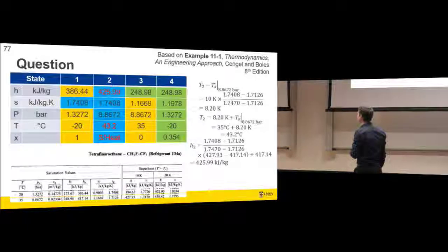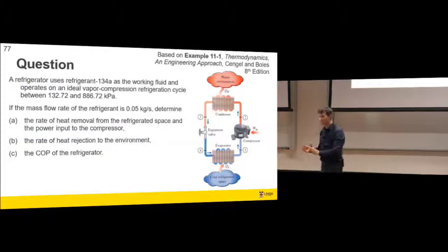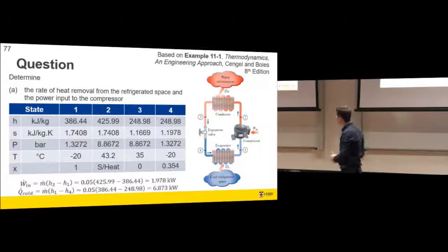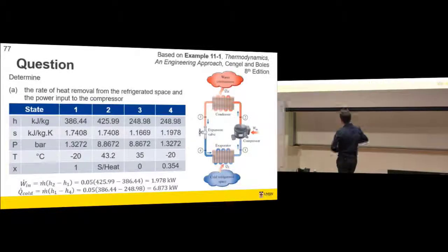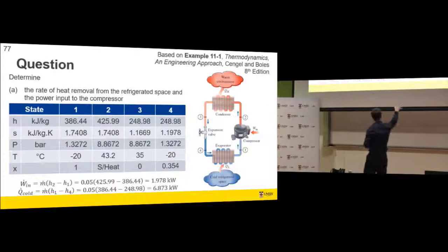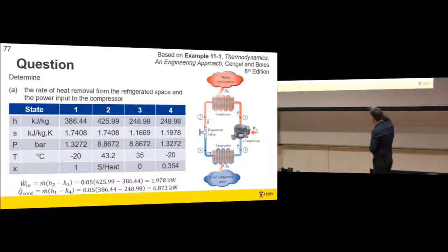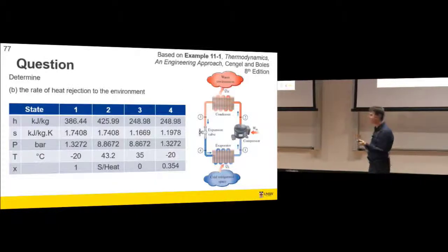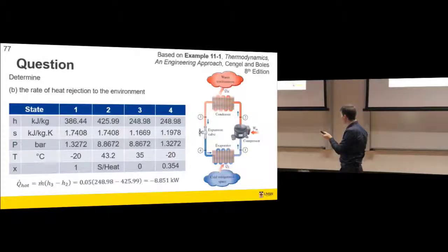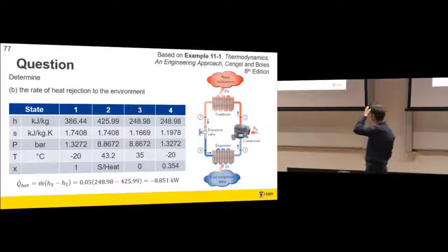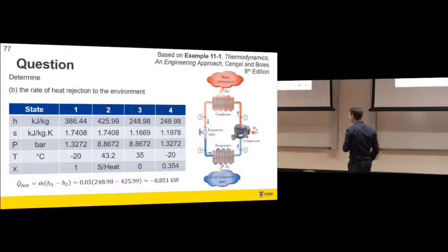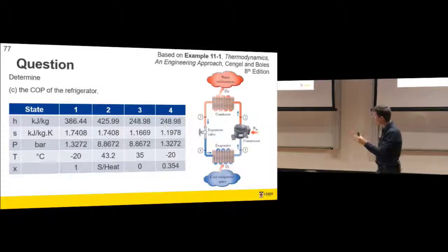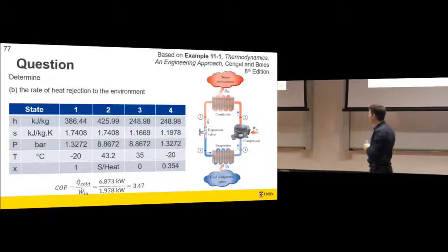Now, what were the things wanted? Rate of heat removal from the refrigerated space - Q-cold equals mass flow rate times the difference in enthalpies. Power input to the compressor - mass flow rate times the difference in enthalpies across the compressor. Rate of heat rejection to the environment equals mass flow rate times the enthalpy difference across the condenser, or equivalently Q-L plus work in. Coefficient of performance - what we want is heat drawn out of the cold space divided by work into the compressor. We get a COP of about 3.5.